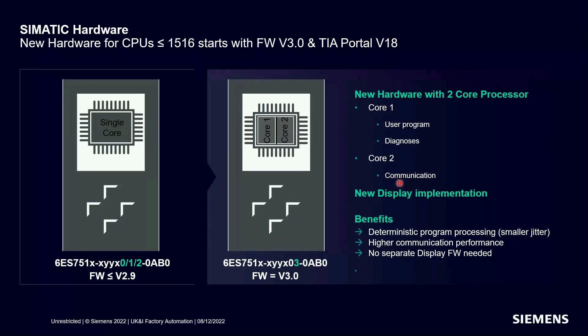This ensures we're ready for the OT layer to meet the IT layer, getting data from our process or machine ready to feed into the cloud, edge, or analytics platforms. Offloading communication tasks from the main CPU core supports more deterministic program processing. Core two focuses on TCP/IP, OPC UA, MQTT, and other protocols that give operational transparency, while PROFINET is handled by its own dedicated ASIC.